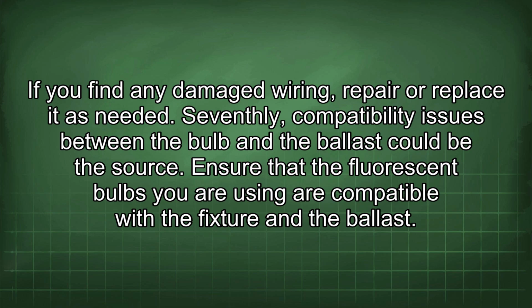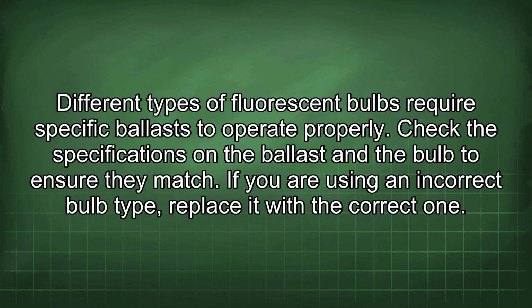Seventhly, compatibility issues between the bulb and the ballast could be the source. Ensure that the fluorescent bulbs you are using are compatible with the fixture and the ballast. Different types of fluorescent bulbs require specific ballasts to operate properly. Check the specifications of the bulb and the ballast to ensure they match. If you are using an incorrect bulb type, replace it with the correct one.